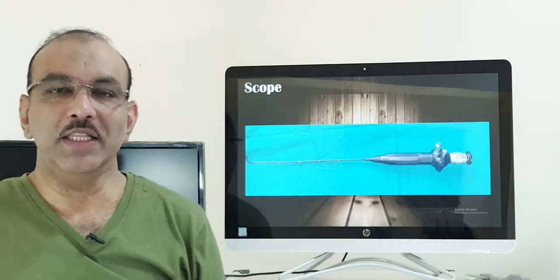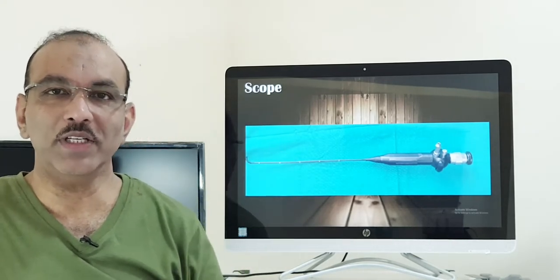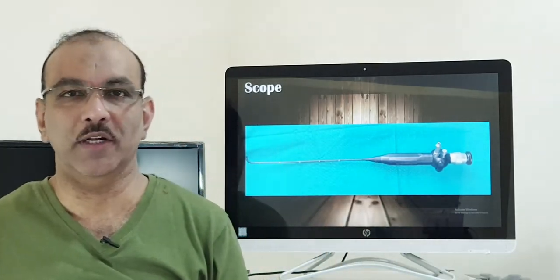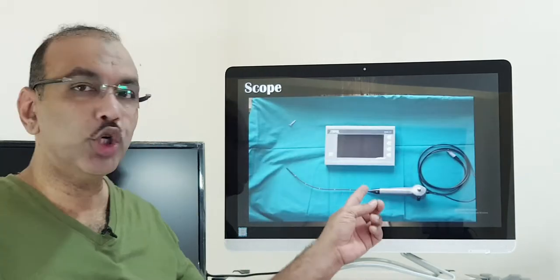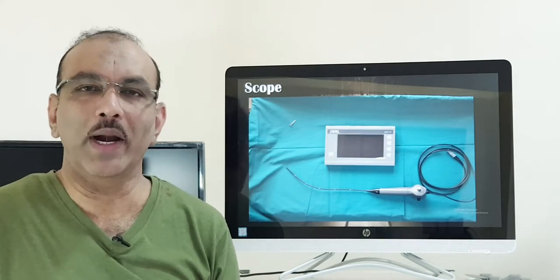This endoscope comes in two types. One is a portable one, and the other one is fixed to a specific endoscopy room. The fixed one — if you want to shift it, the whole endoscopy unit has to be shifted. The portable endoscopy is the size of a small suitcase, but it is portable.